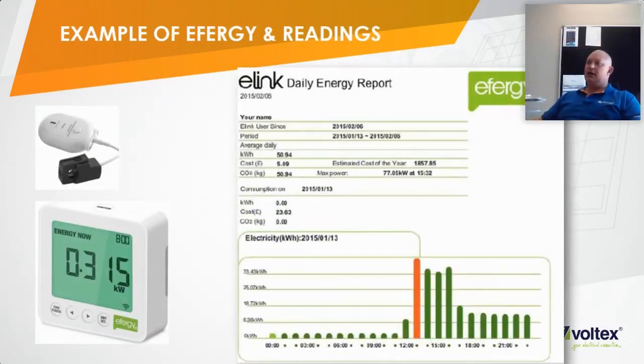Example of the energy meters and energy readings. This is the common EFERGY report that you would get. On the left-hand side of your screen, you'll see the physical little monitor. That's the receiver unit that's got the monitor on it, and the sender unit with the CT, the current transformer, is right above it. The current transformer is installed inside your distribution board, and the receiver unit with the little monitor can be placed within 5 to 10 meters from the DB board, on a fridge or on a shelf, where you've got access to it.